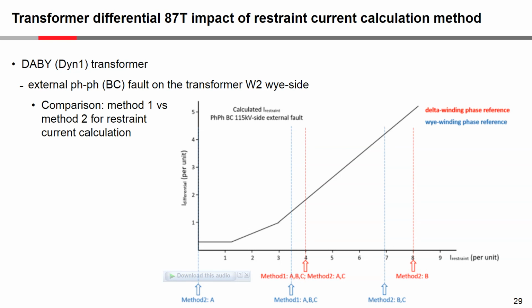So all we've done here is take exactly the same external fault and see, based on how the restraint current is calculated, where the restraint current would be on the x-axis for the delta side used as phase reference versus the Y side used as phase reference.